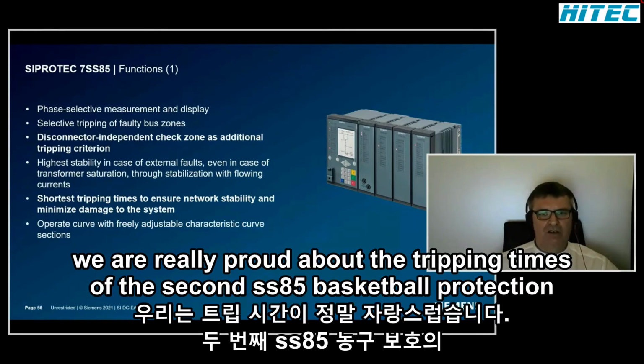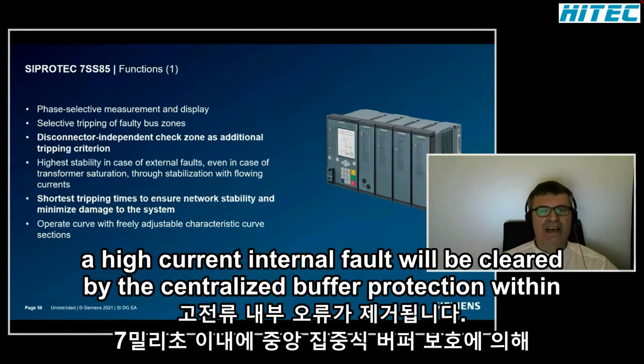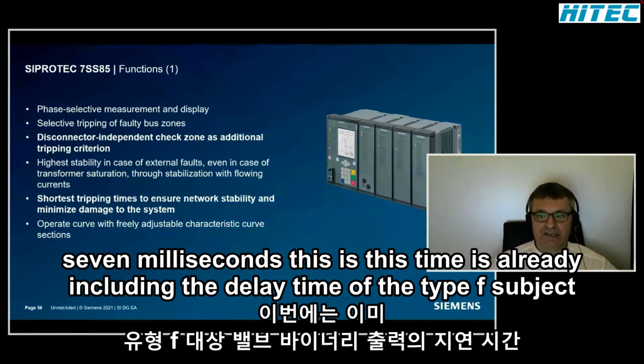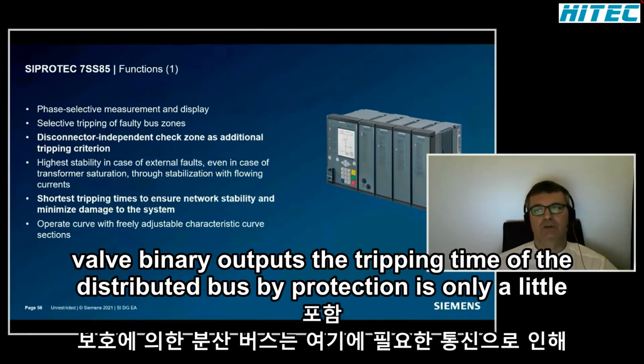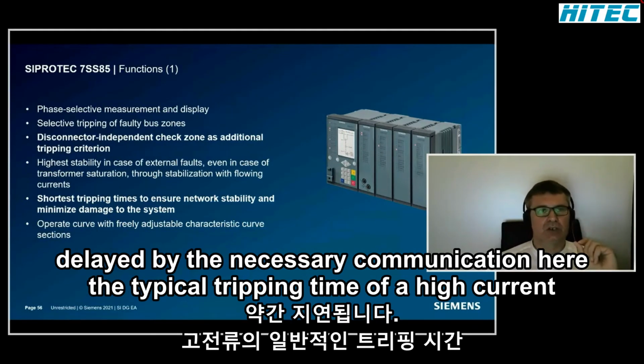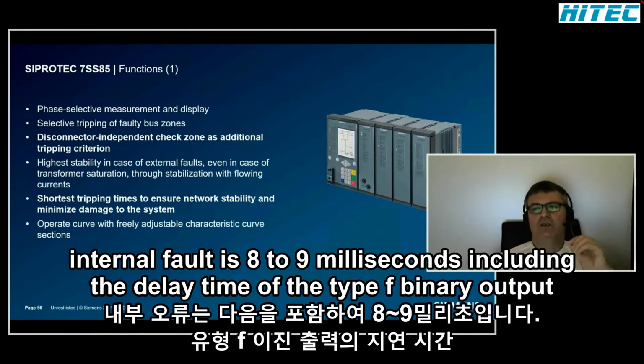We are really proud about the tripping times of the 7SS85 busbar protection. A high current internal fault will be cleared by the centralized busbar protection within 7 milliseconds. This time is already including the delay time of the Type F SIPROTEC 5 binary outputs. The tripping time of the distributed busbar protection is only a little delayed by the necessary communication. Here, the typical tripping time of a high current internal fault is 8 to 9 milliseconds, including the delay time of the Type F binary outputs.